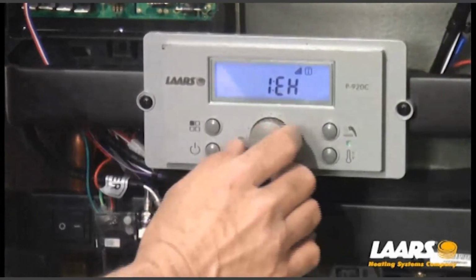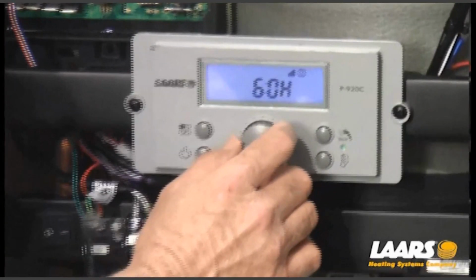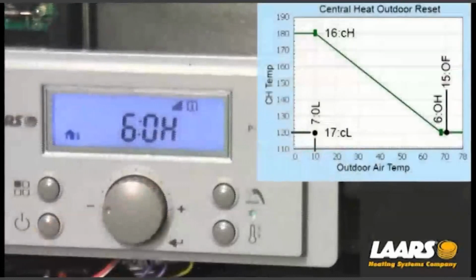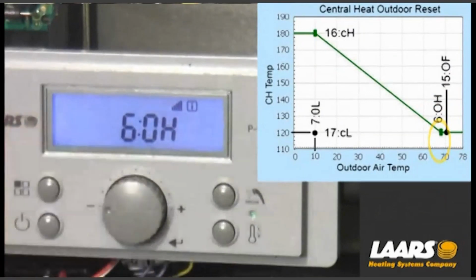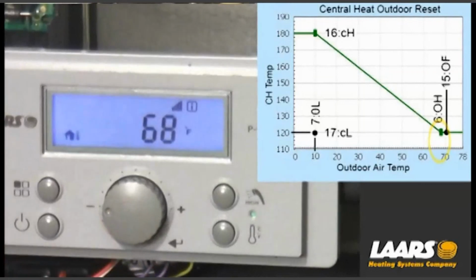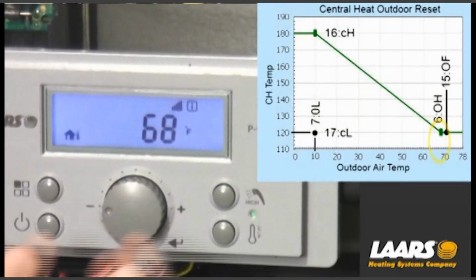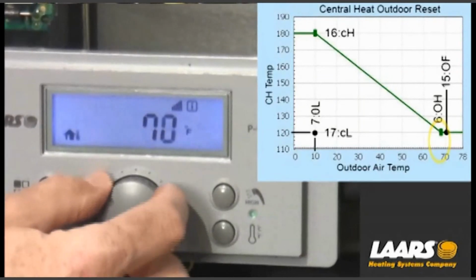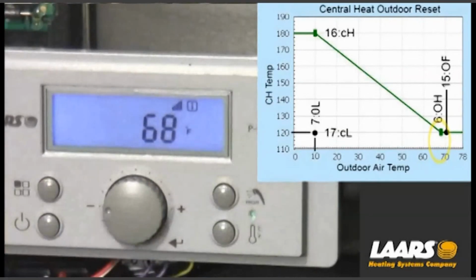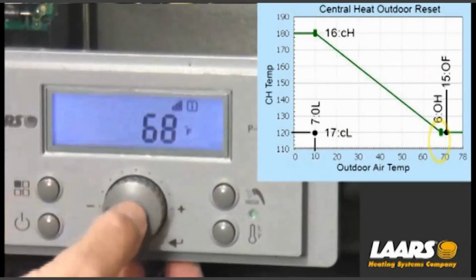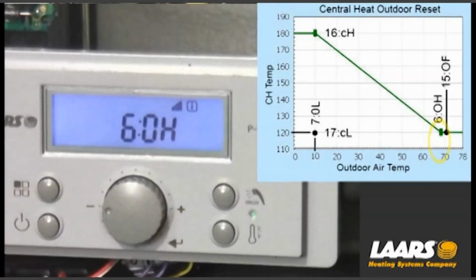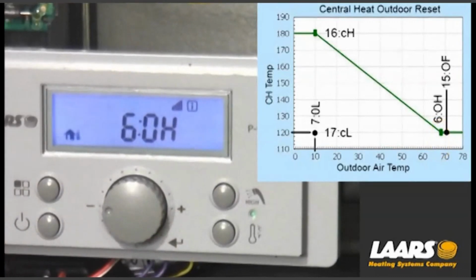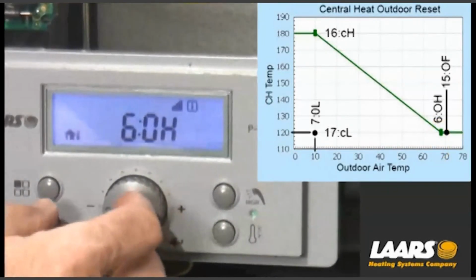The very first thing I want to do is scroll to 6OH. That stands for the outdoor high temperature. All of this information is in the manual and the startup guides. Now with my outdoor high, or 6OH, press the select button, and now I can adjust that. So in this case, I'm going to use 68 degrees as my example. Adjust it to 68, press select, and I've now stored my outdoor high. I'll explain the outdoor reset curve in a minute.